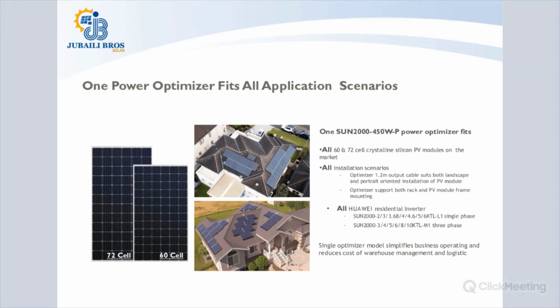Now, finally, this PV optimizer is compatible with the residential inverter solutions from Huawei. That is the single-phase 2 to 6 KTL and the three-phase 3 to 10 KTL. It is also compatible with the 12, 15, 17, and 20 KTL. So, which means its compatibility runs right from the residential systems up to 20 kilowatts. And even most recently, Huawei has upgraded its 30, 36, and 40 kilowatt inverters, which has made them also compatible with the PV optimizer systems. So the interesting news is that the PV optimizers are compatible for all systems from 2 to about 40 kilowatts using the Huawei inverters. And that is great news for installers and project developers alike.